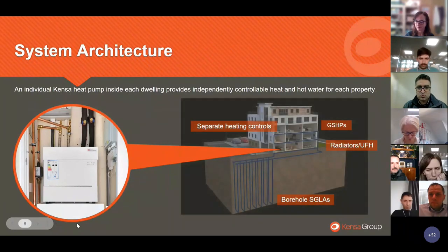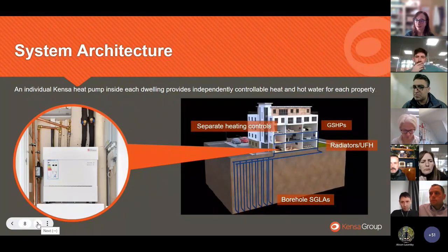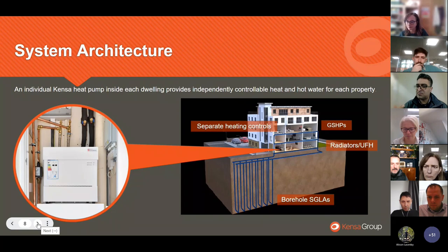In terms of system architecture, each property has its own heat pump, so there isn't a plant room or anything like that. If that property requires heat, it collects ambient energy from the ground loops, represented by the vertical pipes going down. That energy goes into the heat pump, which compresses a large amount of ambient energy into a small amount of usable heat. Each property has independent control of its heating and hot water system, meaning if another property wants heating out of season, they can have it without requiring the whole plant to operate. There tend to be no moving parts outside the property - you have a heat pump with a circulatory pump and divert valves within the building, and outside it's all pipes connected to risers that go up inside blocks. That's what the system infrastructure looks like.